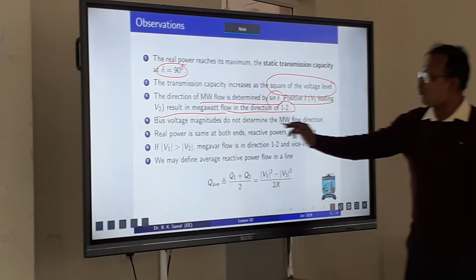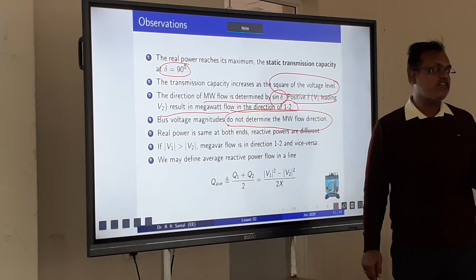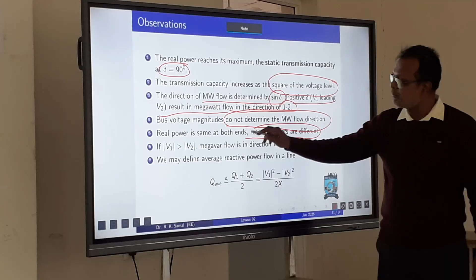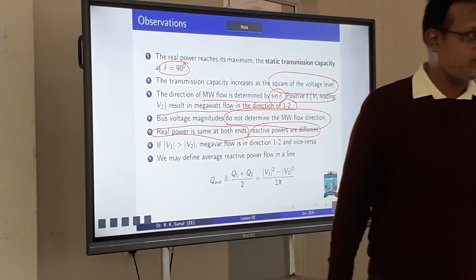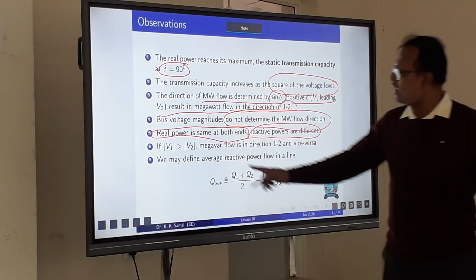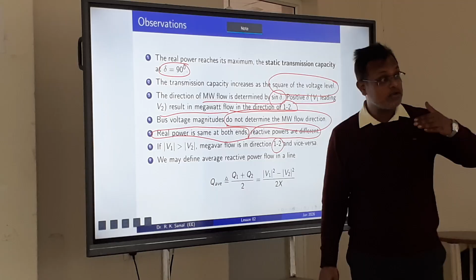Okay. Voltage magnitudes do not determine the megawatt flow direction. You cannot increase the voltage and expect the power flow to increase. Real power is the same at both ends, reactive powers are different. Real power is the same at both ends under the assumption of no loss. Whatever you transmit, you receive, provided there is no loss. If V1 is greater than V2, the reactive power flow is in the direction of 1 to 2 and vice versa. So when voltage is higher, the reactive power flow happens, not the real power.